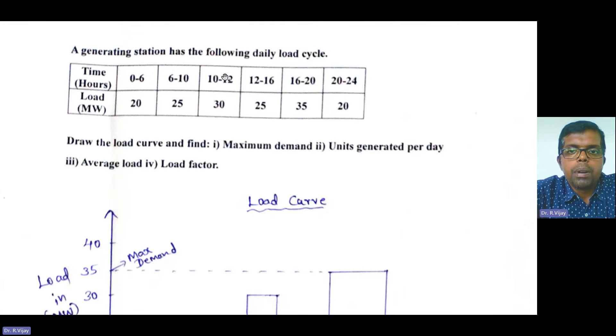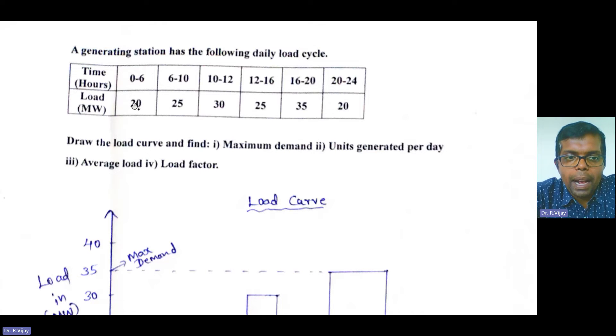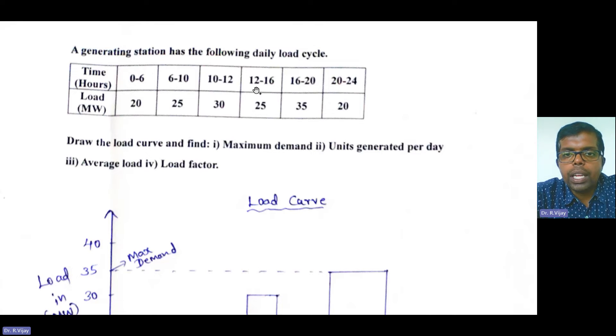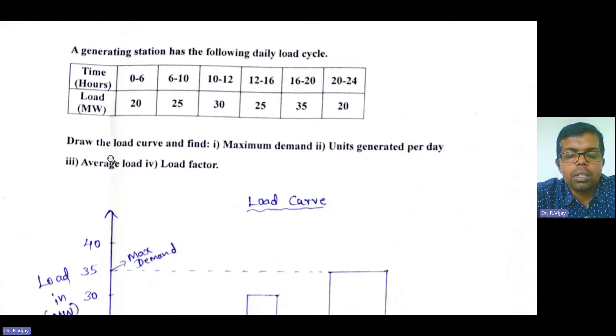Today we are going to solve a problem on the load duration curve. A generating station has the following daily load cycle: 0 to 6 hours is 20 megawatt, 6 to 10 is 25 megawatt, 10 to 12 is 30 megawatt, 12 to 16 is 25 megawatt, 16 to 20 is 35 megawatt, and 20 to 24 is 20 megawatt. We have to draw the load curve and find the maximum demand, units generated per day, average load, and load factor.